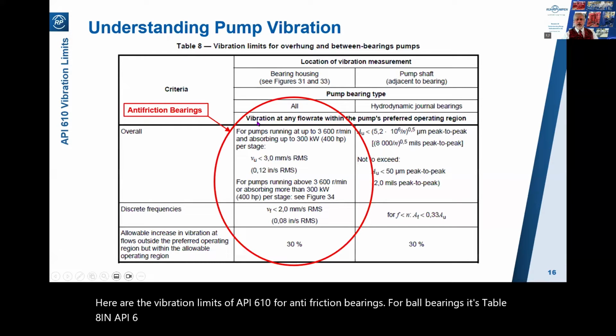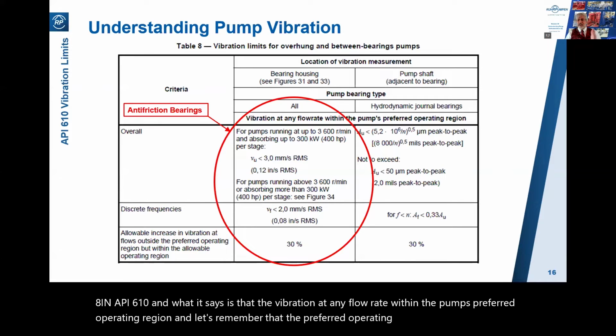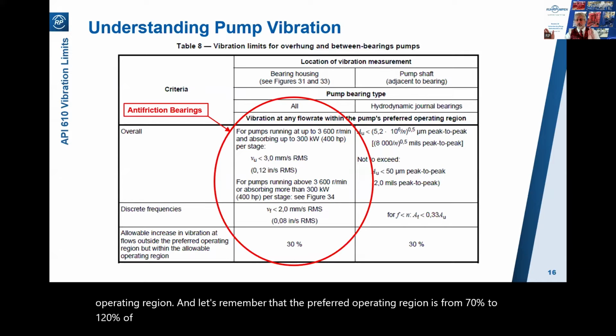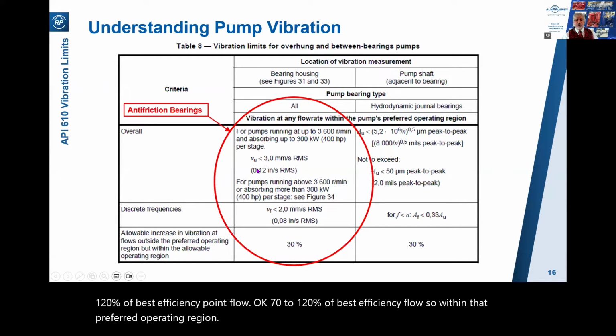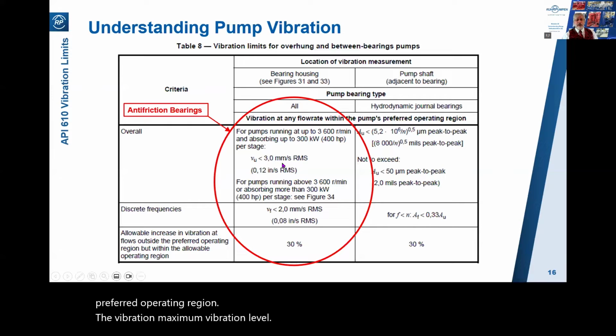And what it says is that the vibration at any flow rate within the pump's preferred operating region, and let's remember that the preferred operating region is from 70% to 120% of best efficiency point flow. Okay, 70 to 120% of best efficiency flow. So within that preferred operating region, the maximum vibration level shall be 3 millimeters per second, root mean square, which is 0.12 inches per second, root mean square.